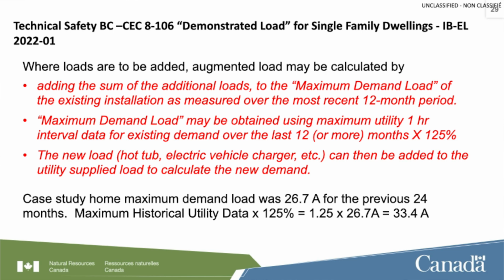So the augmented load may be calculated by adding the sum of additional loads to the demand load as measured over the 12 months of historical usage. The maximum demand load may be obtained by multiplying that number by 125%, building in a safety factor. Then the new load — hot tub, electric vehicle charger, etc. — can be added to the utility-supplied load to calculate the new demand.